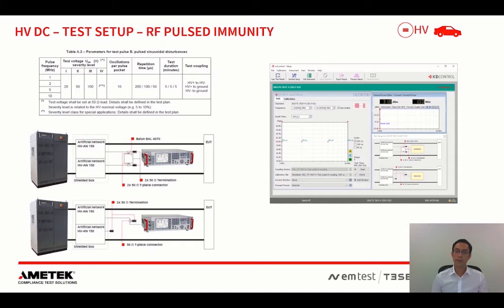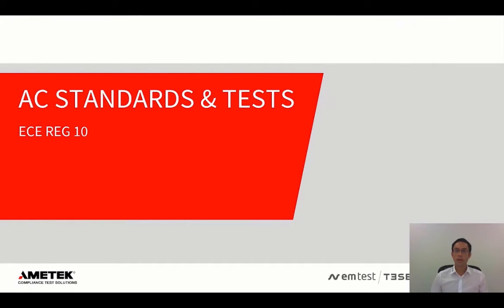So required for the test setup is again obviously a source that provides the DC, and then we have an RF signal generator, which is shown here in the middle, plus some coupling device. The coupling device couples the RF disturbance signal onto the high voltage DC line. And as I said, it's a high frequency test between 1 and 10 MHz. Now, this concludes the part on the high voltage DC tests.